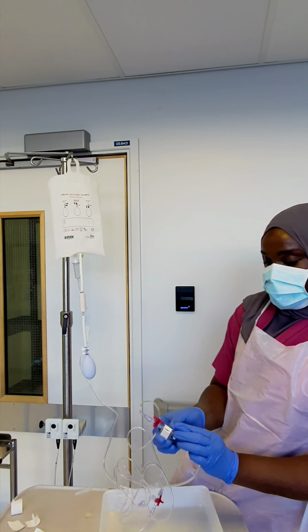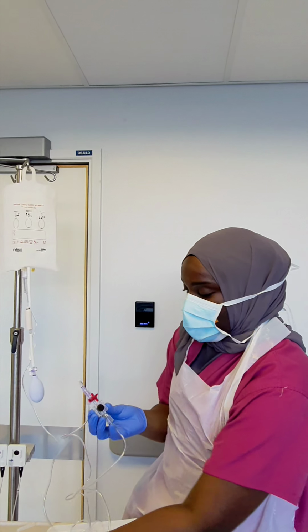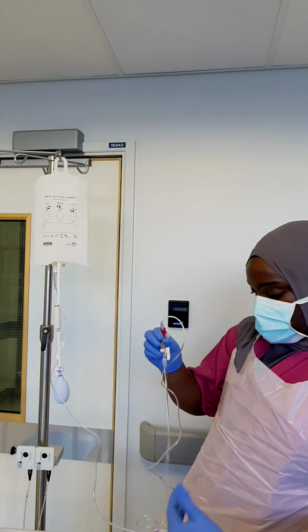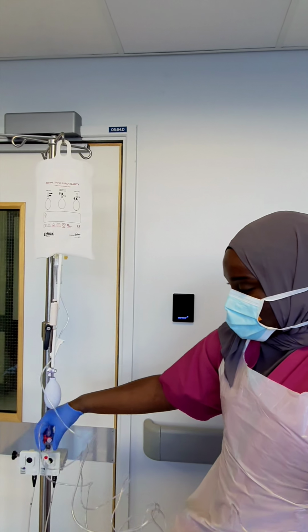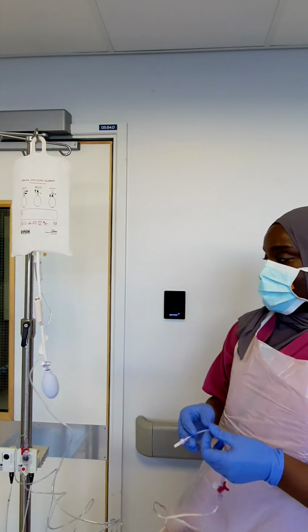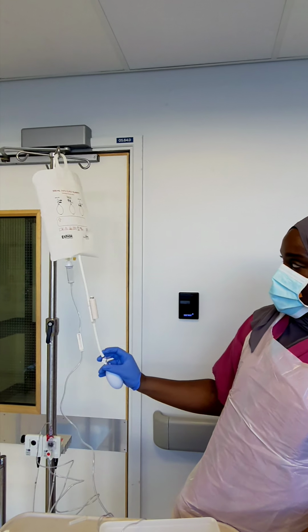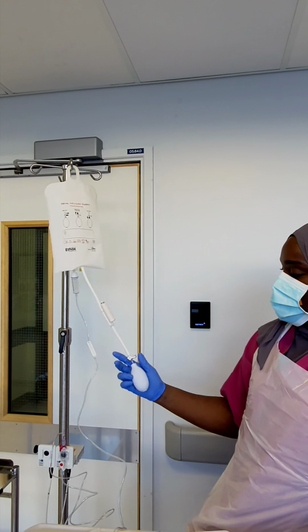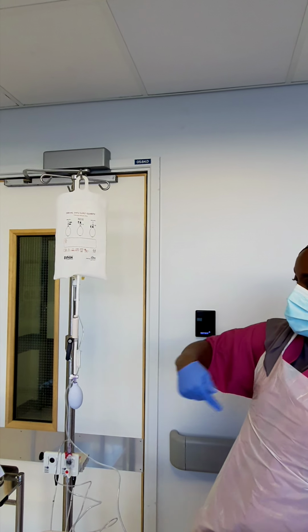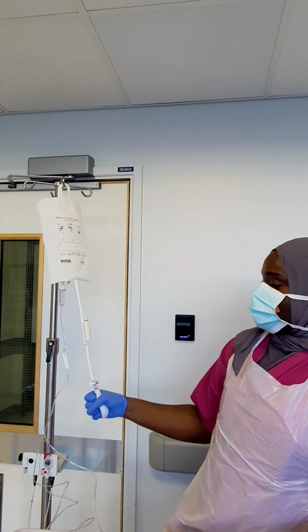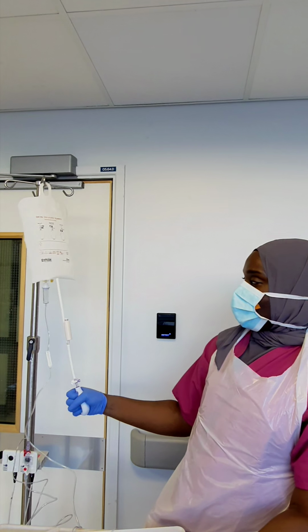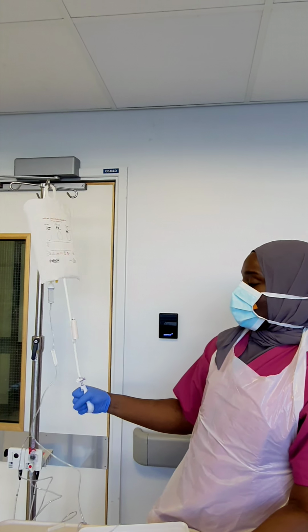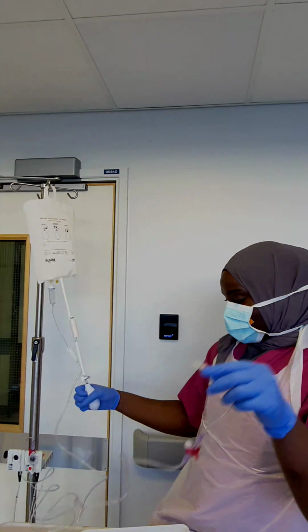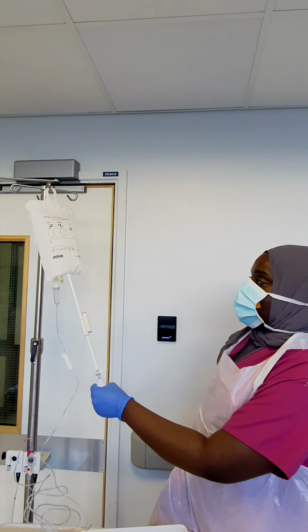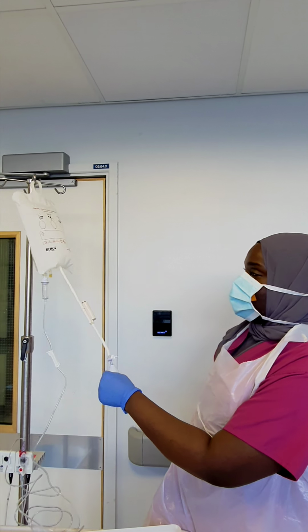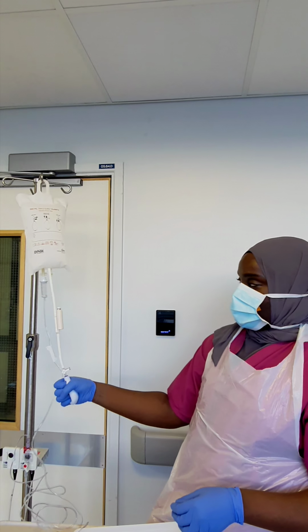So we will also detach this white thing from the back of the transducer set. And we are going to clip this in place into the pressure dome. You should hear a little click. And we are going to close the pressure bag to the open port, which would mean we'll be able to pump air in without air coming out this way. So we're going to pump. It does take a while. Switch arms if you need to.